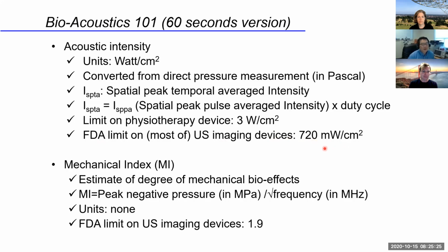Another important jargon that you will hear is a mechanical index, MI. It estimates the degree of a mechanical bioeffect, such as cavitation, being represented by peak negative pressure in megapascal divided by the square root of frequency in megahertz. Interestingly, it is unitless number, and FDA limit on ultrasound imaging device is 1.9.